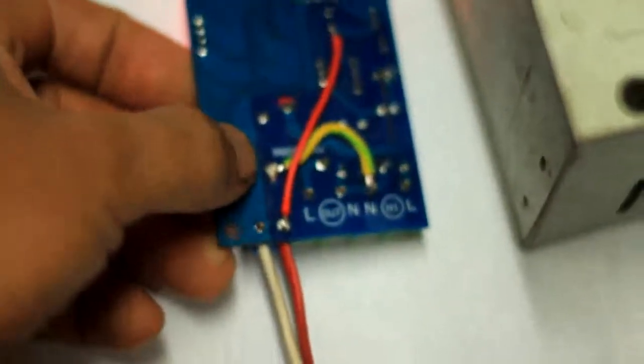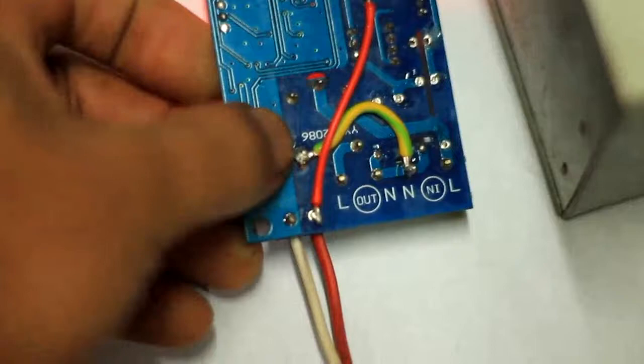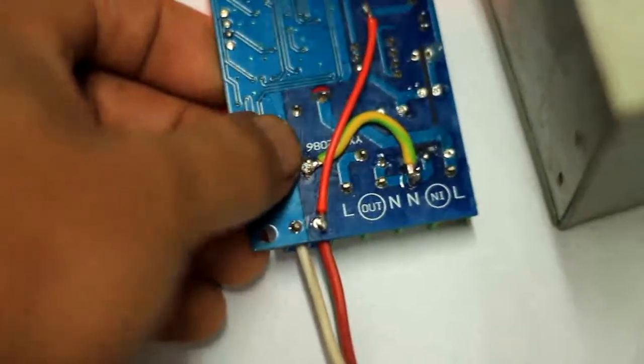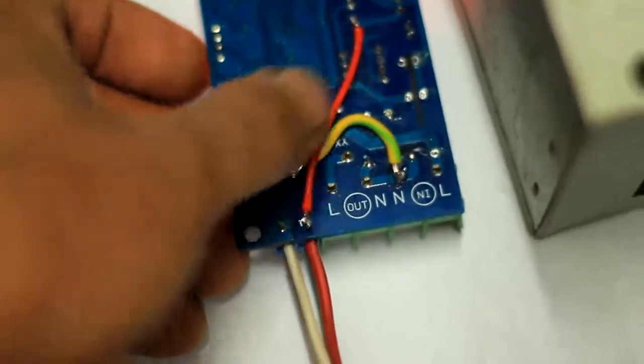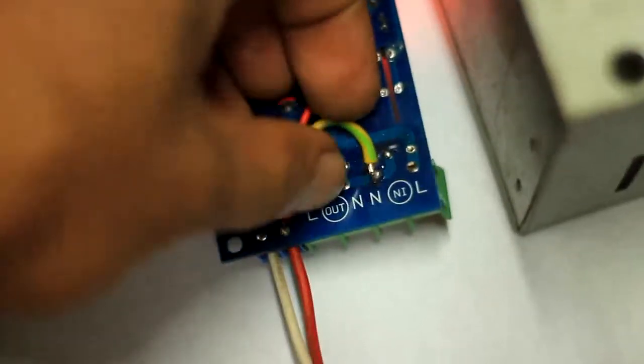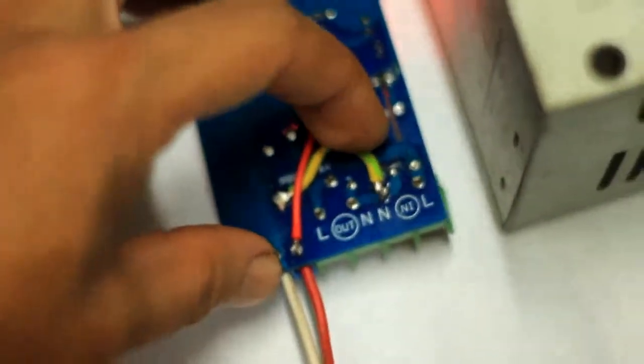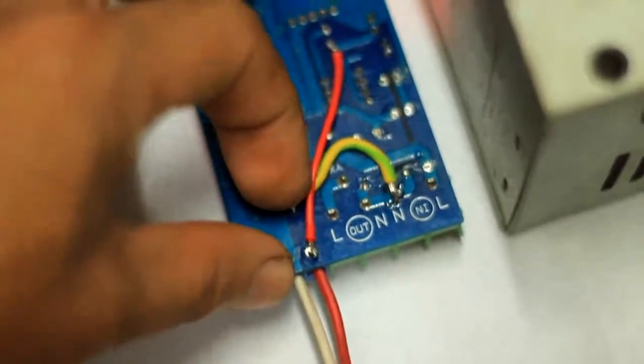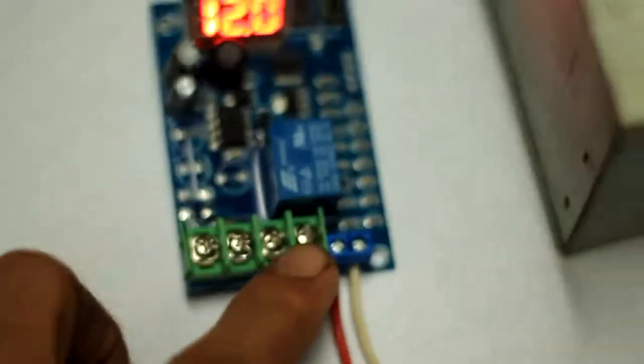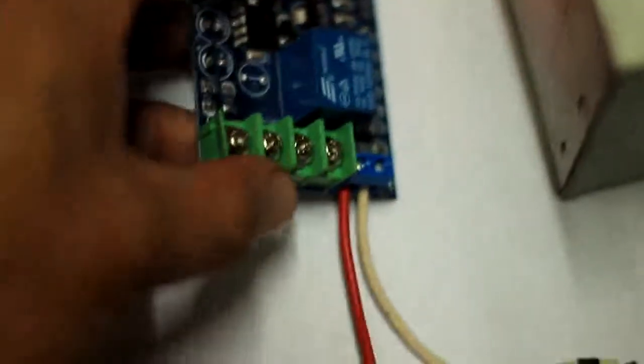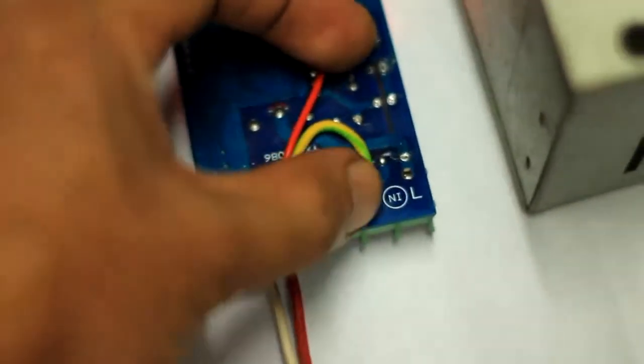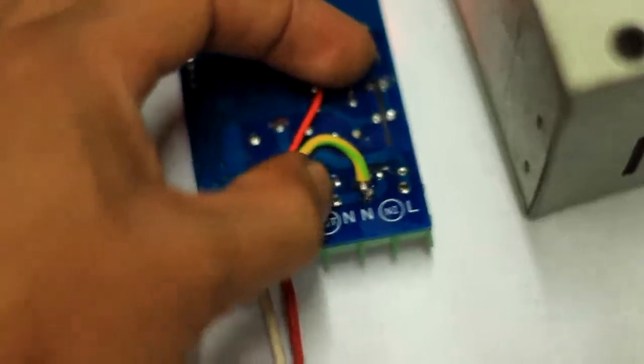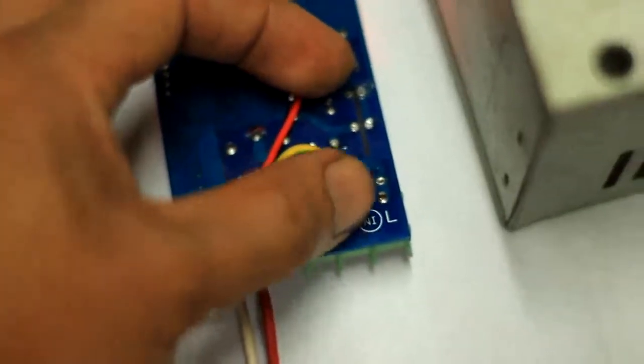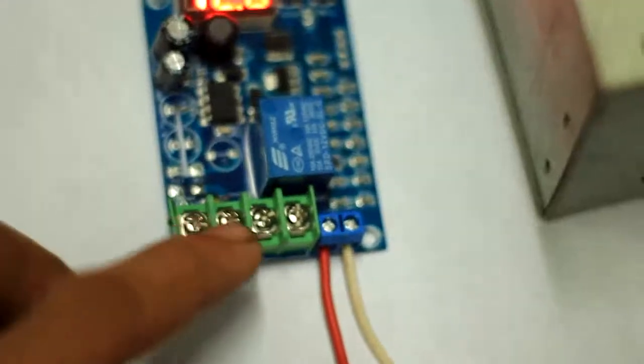So on the normally closed side, the one without tracing, I connected a bigger wire that can handle 10 amperes, since the relay is rated for 10 amperes. I connected that wire and jumpered it to our connector here—so instead of 4 separate connectors, the middle two are now connected to each other, allowing us to use these connectors for our load.